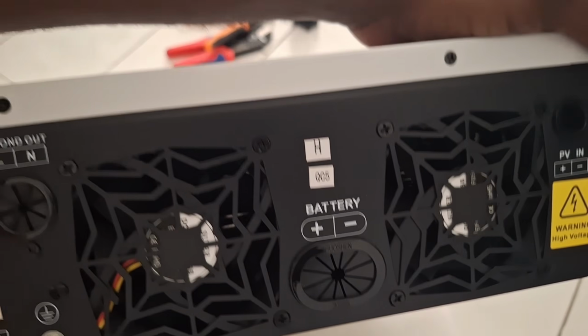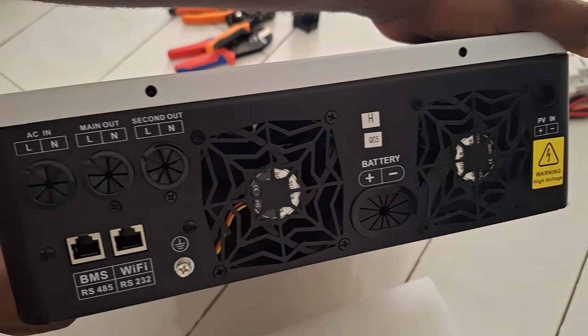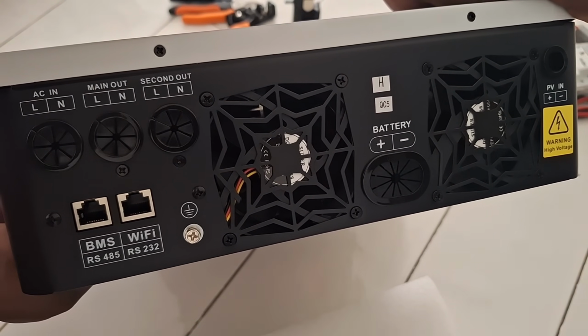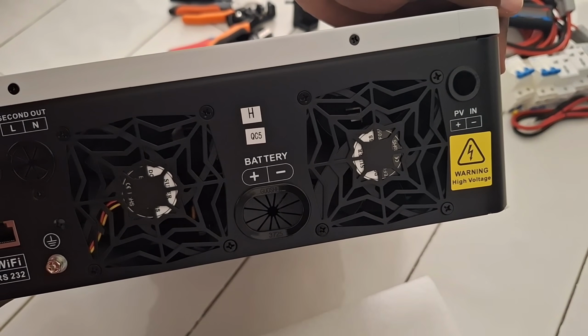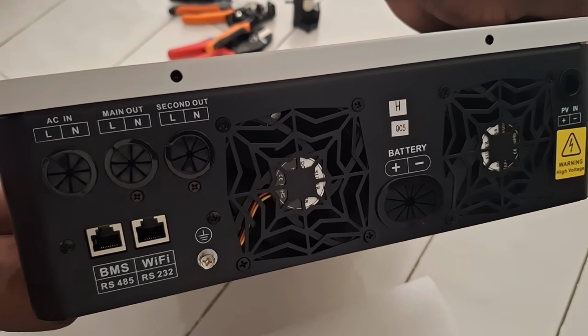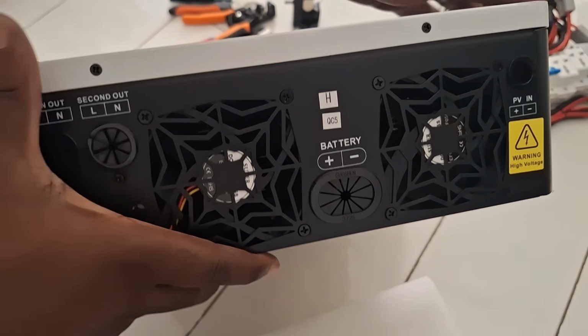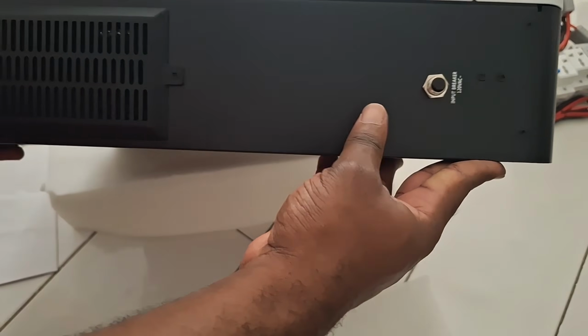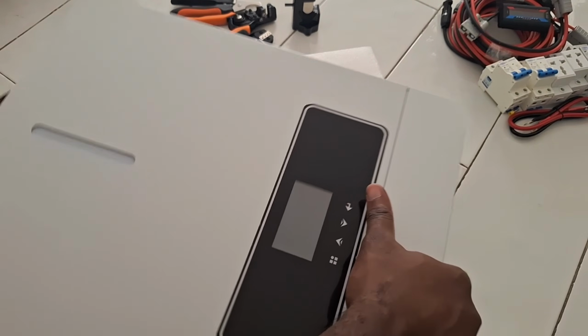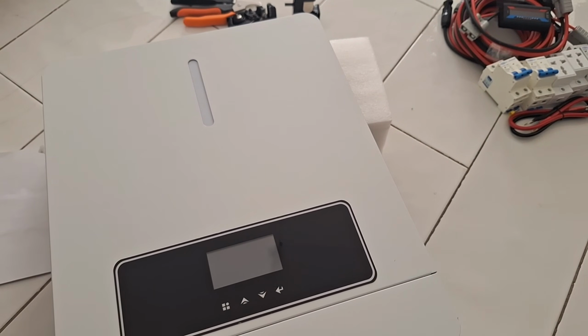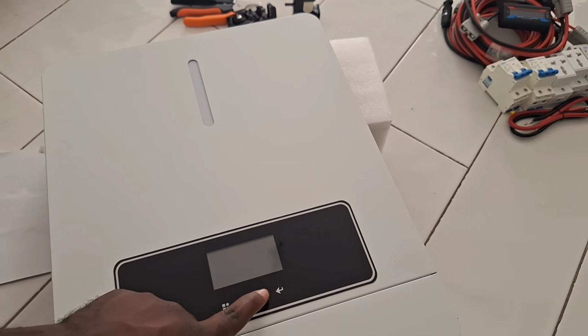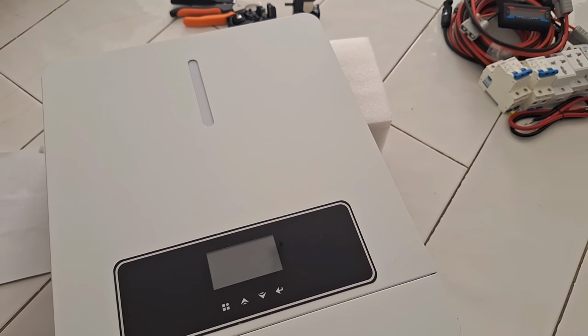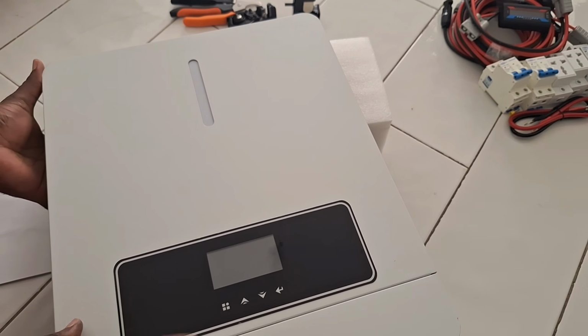When it comes to the AC input or the input from the grid, the max current it will take is 40 amps, and the operating voltage is 110 to 120 volts AC. For this type of inverter, you must be using a 24 volt battery, and the max battery current is 150 amps. When it comes to the AC output, you're looking at a nominal output current of 30 amps.